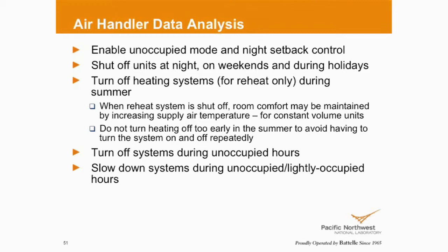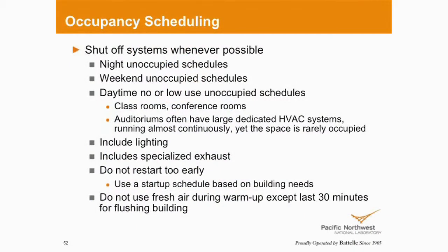Can we slow them down if I can't shut them off, like I just talked about? Can I change my static pressure set point? Can I do something at the terminal box level? Some areas that we would recommend, we see as challenges or opportunities: classrooms, conference rooms. This conference room, if it's got its own dedicated VAV box, can I put a schedule on this room?